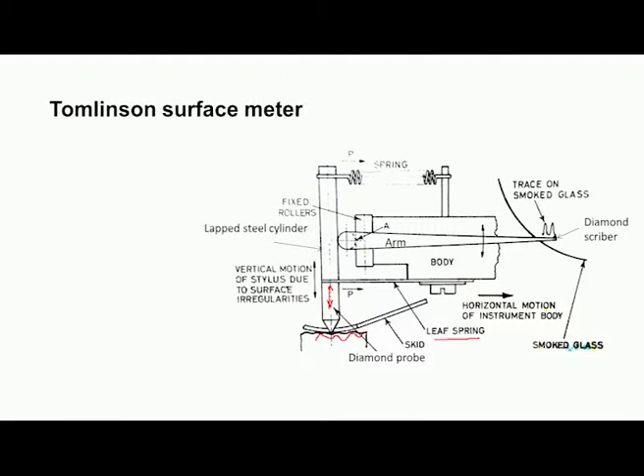So, both the horizontal motion of the instrument body and the vertical motion of the lapped cylinder are combined here to get the surface profile. The vertical motion of the lapped steel cylinder is magnified by using a longer arm, whereas the horizontal motion is not magnified. Now, we can take this profile, and if required it can be further magnified, and then the various parameters can be calculated. So, this is how a Tomlinson surface meter works.